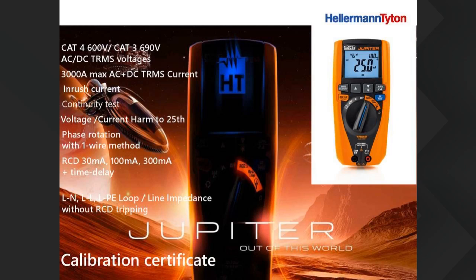Now, the next pointer, it's called RCD testing. Now, RCD stands for residual current device. So that is basically an earth leakage. We in South Africa know it as earth leakage. Now, RCDs, so this meter can measure earth leakages from 30 milliamps, 100 milliamps, 300 milliamps, plus it can measure the time delay.